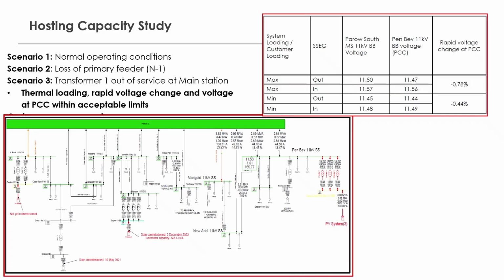We typically do this from our side. Luckily, we do have the skills, expertise and resources internally to be able to continue with the studies. So typically we do the hosting studies. We've got various scenarios. These are not all the scenarios, but just to mention some of them. For example, we would do the load flow studies under normal operating conditions. Then we will do it where we lose the contingency feeder, and we will see how the system basically operates under those conditions.